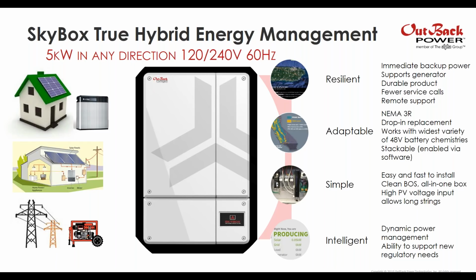SkyBox supports PV voltage ranges as low as 250 volts and as high as 600 volts, a very wide voltage input range, so you can set your string sizing for whatever is appropriate for your situation. Finally, SkyBox provides dynamic power management, the ability to measure power at all 5 of its ports, and we also have the ability to support new regulatory needs via firmware downloads. So anytime the grid regulations change or there's a new change in utility rates, we can support those via firmware updates.